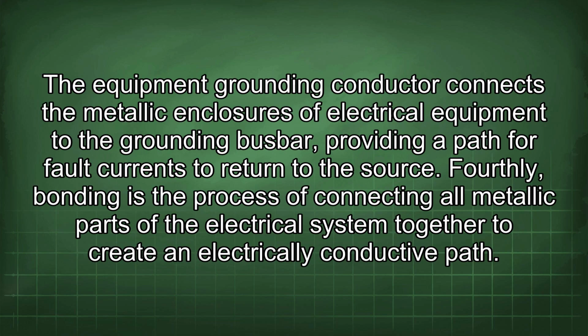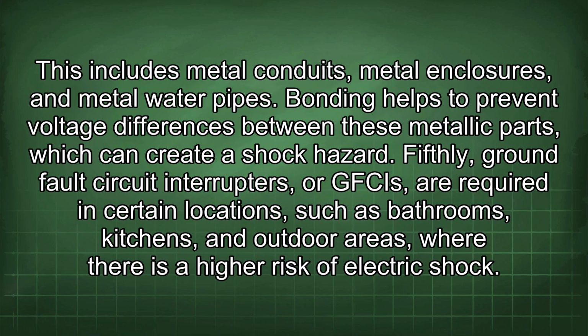The equipment grounding conductor connects the metallic enclosures of electrical equipment to the grounding busbar, providing a path for fault currents to return to the source. Fourthly, bonding is the process of connecting all metallic parts of the electrical system together to create an electrically conductive path. This includes metal conduits, metal enclosures, and metal water pipes. Bonding helps to prevent voltage differences between these metallic parts, which can create a shock hazard.